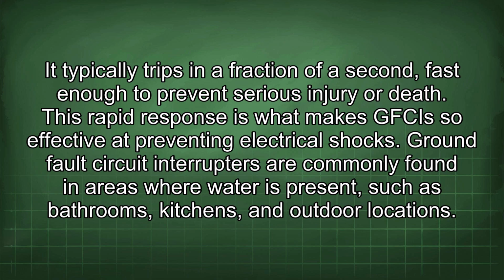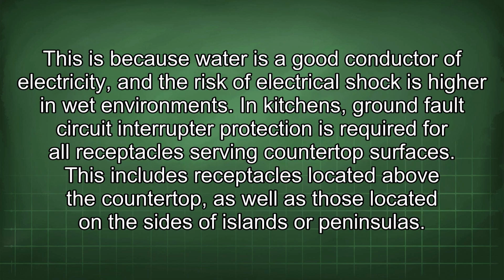Ground fault circuit interrupters are commonly found in areas where water is present, such as bathrooms, kitchens, and outdoor locations. This is because water is a good conductor of electricity, and the risk of electrical shock is higher in wet environments. In kitchens, ground fault circuit interrupter protection is required for all receptacles serving countertop surfaces. This includes receptacles located above the countertop, as well as those located on the sides of islands or peninsulas.